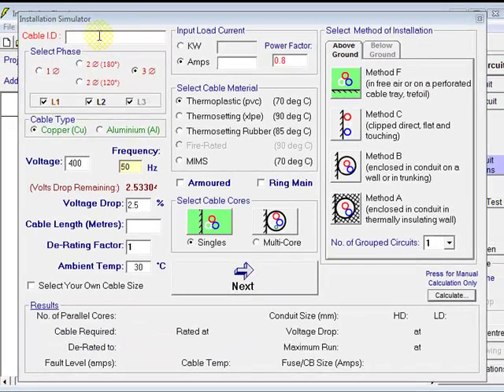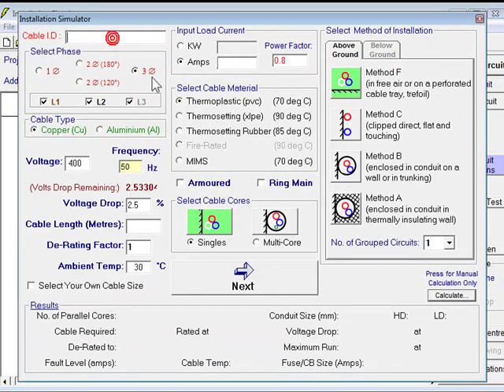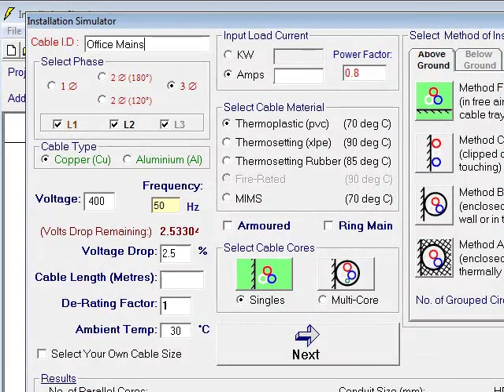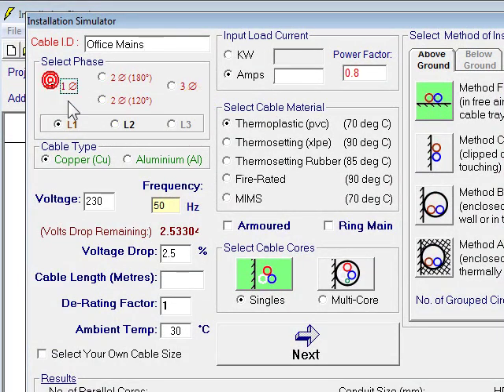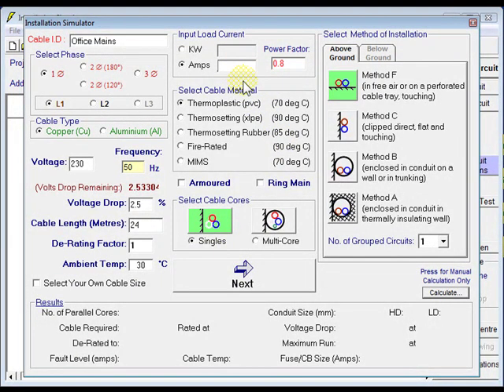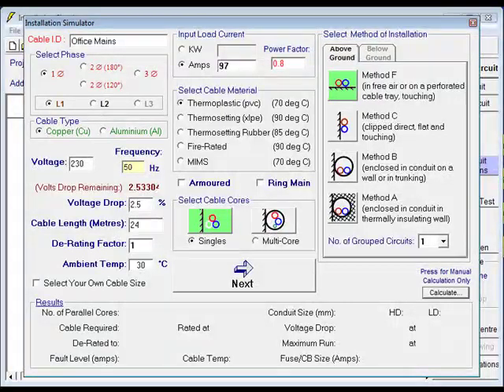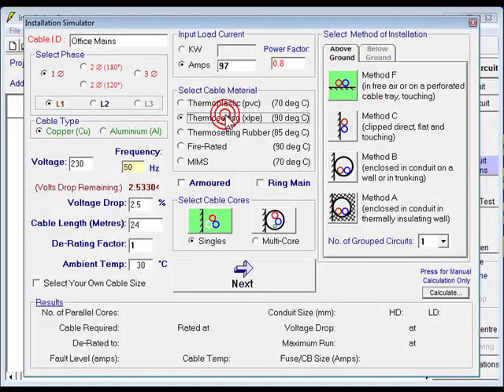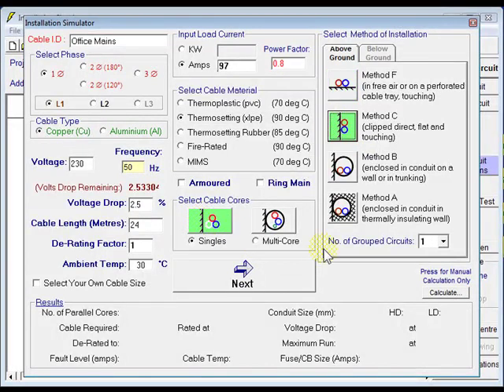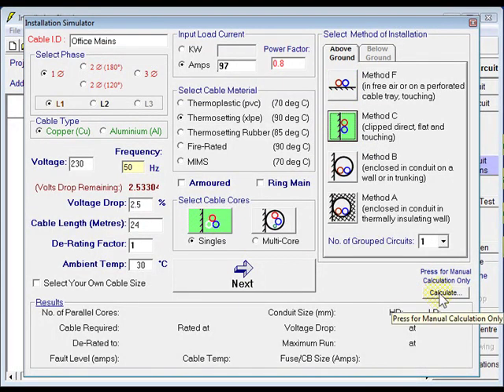Give this cable a name, call it office mains. It'll be single phase, 230 volts. Length of that run, 24 meters. Current on that load, the load on that run, 97 amps. XLPE 90 degrees, that'll be clipped direct, in singles. We can come over here and calculate that.